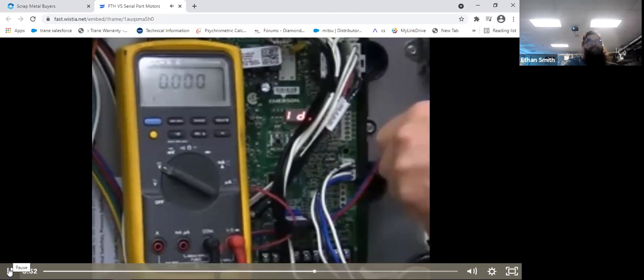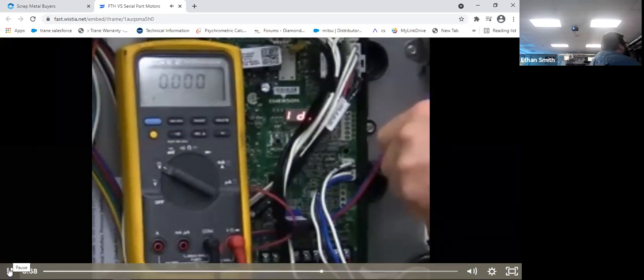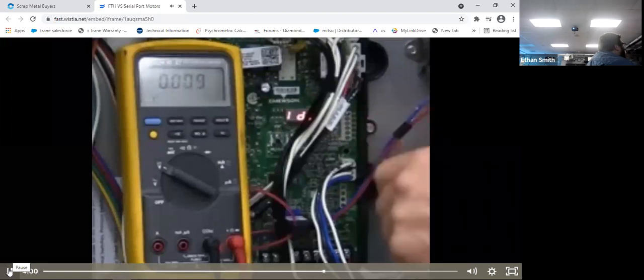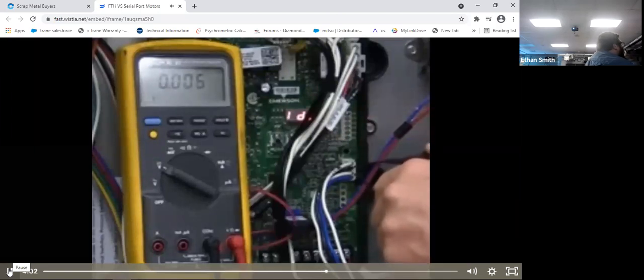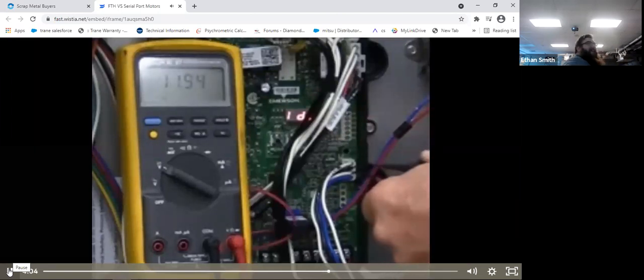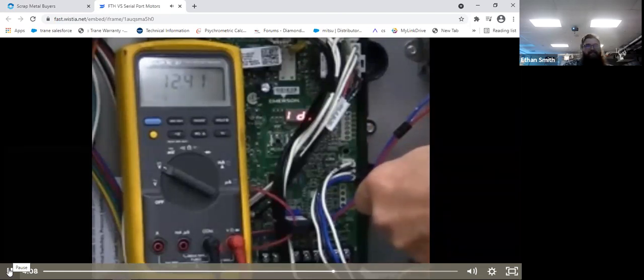If I have 12 volt source, but I do not see any voltage on my transmit, then I'm going to condemn the board. If I do see pulses on my transmit, I'm going to go to my RX, which is the other white wire just below my ground. And here I can see my RX is very similar to my source voltage, and it is tied to the same power supply. So if I see that my RX does not change in voltage, I know that my motor is not sending any information back to my control board.